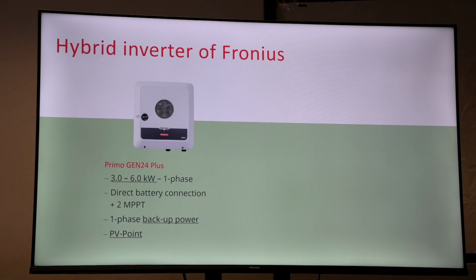You've got 2 MPPT inputs on the inverter, as well as a direct battery connection in the inverter itself. You also have a PV Point. This is when you are utilizing the hybrid capability of the inverter without a battery available. You can pull 3 kilowatts directly through the unit into a small outlet, and then you can do single phase 3 kilowatt availability for 4 hours, for example, without having a battery.